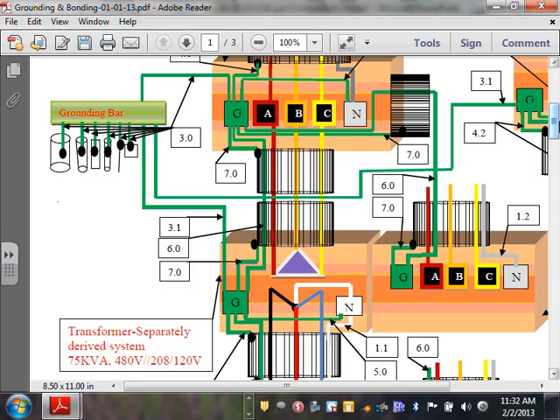The problem is, if I'm an inspector, how can you prove that this is a reliable grounding electrode system? Well, I'm not saying it's a good idea, I'm just saying the code doesn't allow it. I don't think so. I haven't seen it allowed, so it's not allowed. But the building steel in the building is allowed in 2011. So that's why I say the most common practice, unless you have a steel building, is to take a grounding electrode conductor all the way to the source of the grounding electrode system and tie it to it.